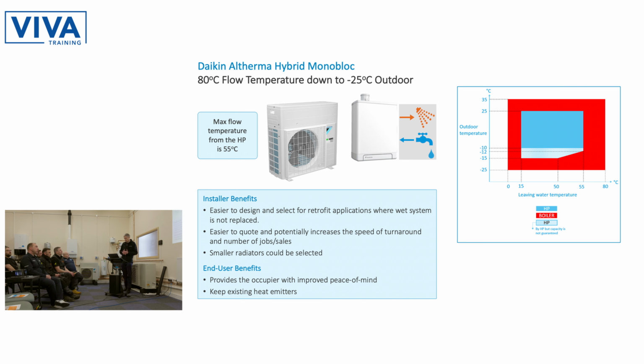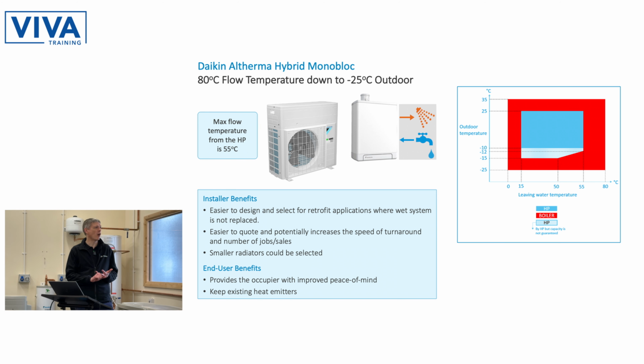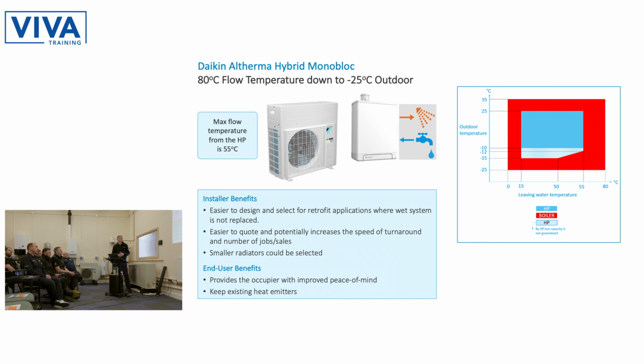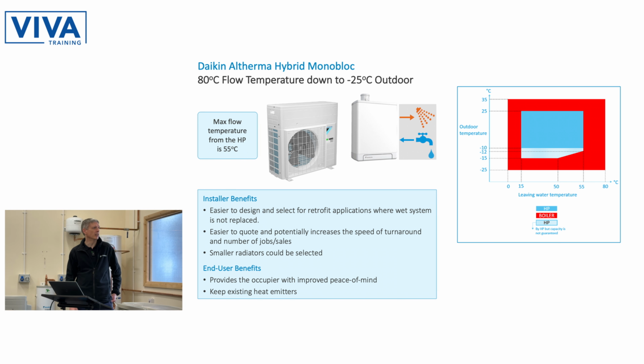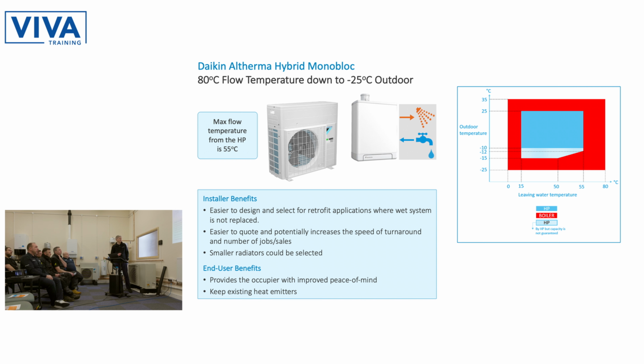One advantage for you with the hybrid being able to operate up to 80: if you're not changing radiators, you haven't got to fit a hot water system, it's easier for you to quote. You know the boiler can do the job, whatever the heating system they've got there at the moment is. So that makes it quicker to turn around quotes. You haven't got to go through the full assessment of the heat loads of each room. Do I need to change the radiators? So that's an advantage for actually getting the job quoted. And if you do need to replace any radiators for whatever reason, then you don't need to select them as large as you might for a heat pump only solution.